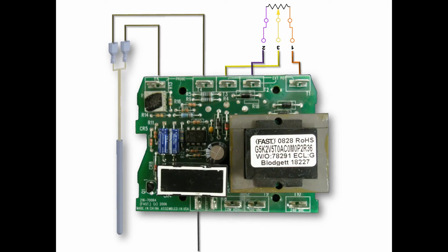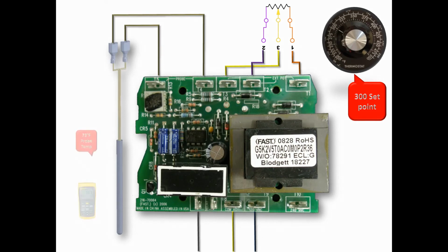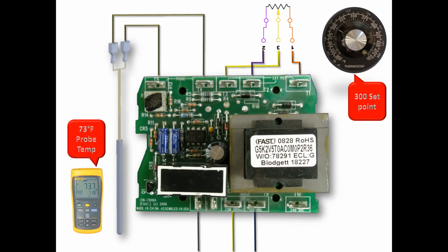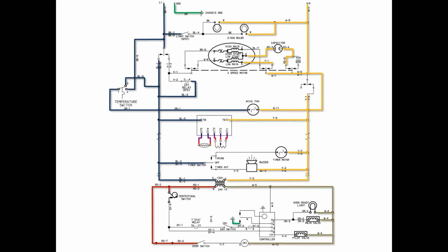Now we see the board's supply voltage, the T6 common to the heat relay from the centrifugal switch, the potentiometer, and the probe. When the temperature set point is above the temperature of the probe, the heat relay closes, sending voltage out from T7. Here we see the potentiometer, probe, and temp control call for heat by closing the heat relay. Because the door is open, no voltage was present at T6, so T7 cannot feed out a signal.